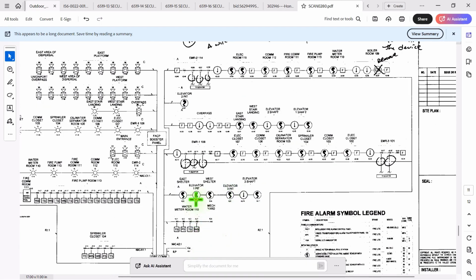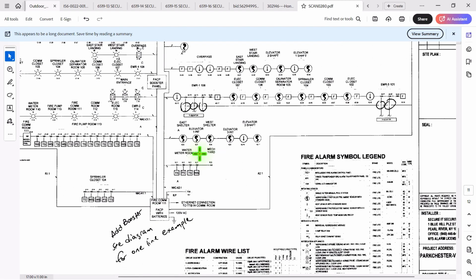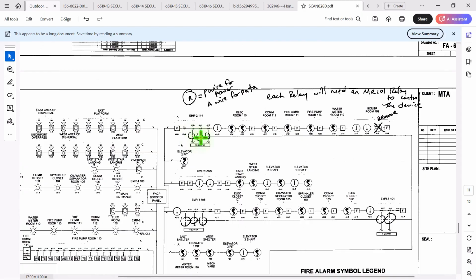For each one of these relays circled, we're going to add another square box for the CR, the control module. So we'll have a relay and a control module. We can't connect anything high voltage to the fire alarm control or any of these modules, and I don't know if they're high voltage or low voltage. So I'll keep it standard using the 2 relays. That's why we're going to have to run 24 volts and data to these guys, just these, and the ones I circled.